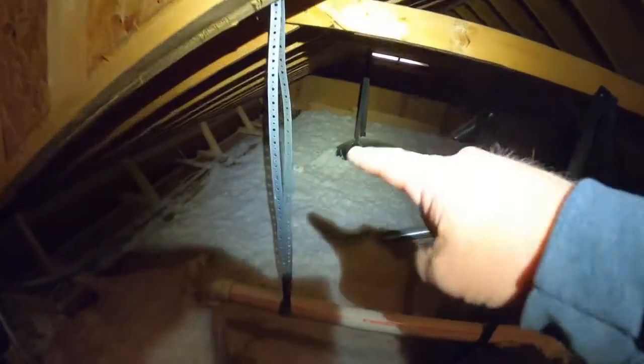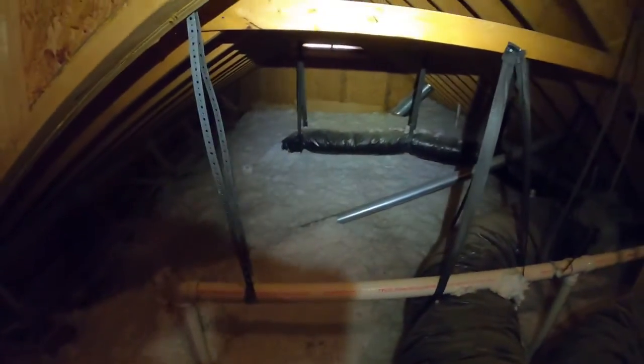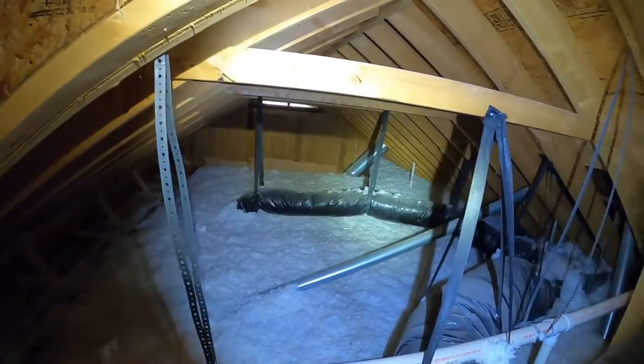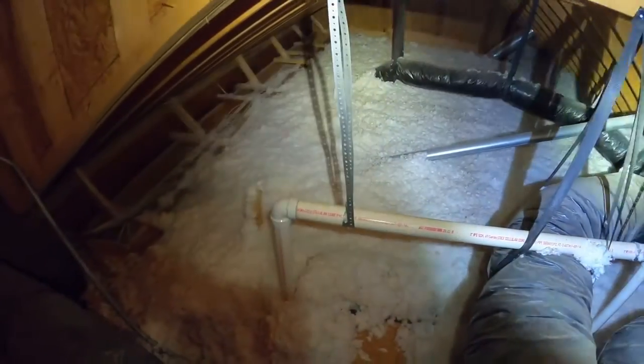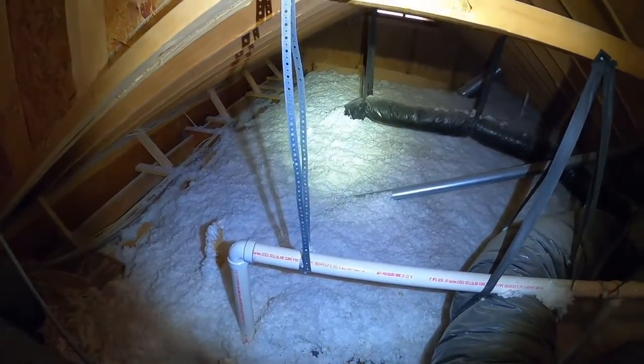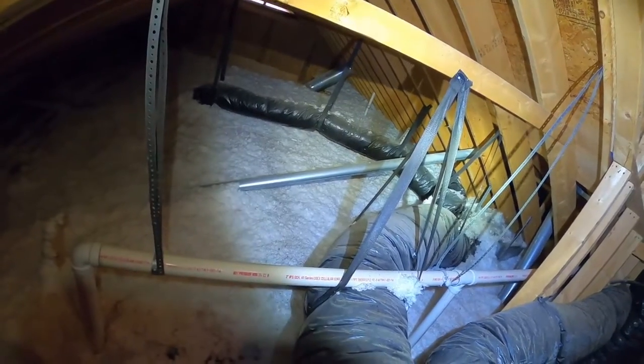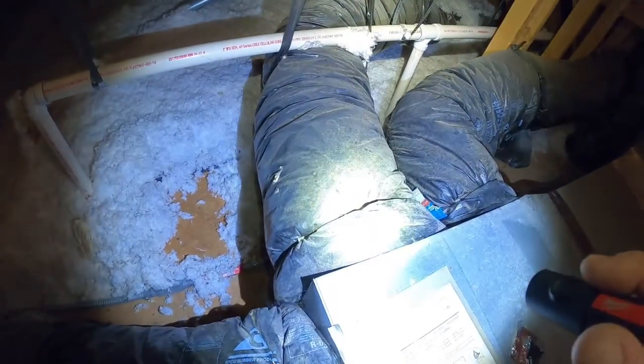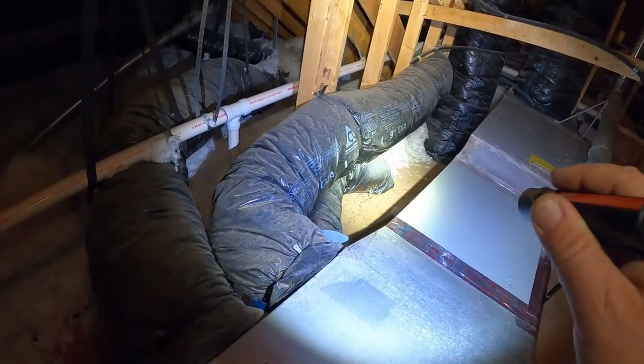So now we're up here doing the airflow balance. This is the second floor. There's a closet in there — this whole area right here goes all the way back across there, comes back across here, comes right back under here. That whole area back there is the closet for the master bedroom — it's a walk-in closet, a regular size bedroom in most houses. It's not blowing any air. There's another one in the master bathroom that's about the same size — also not blowing any air. This one was turned back a little bit, and the one in the laundry room was blowing wide open; he wanted that one off.